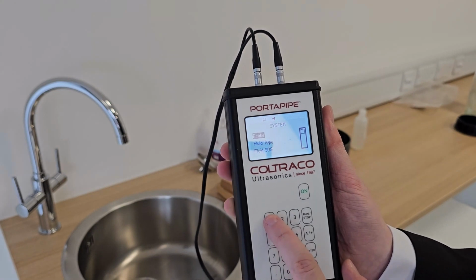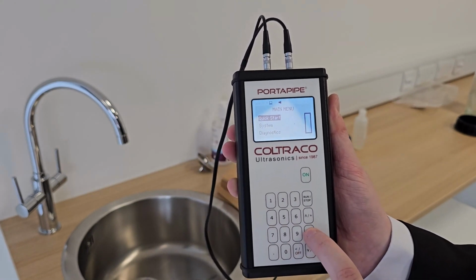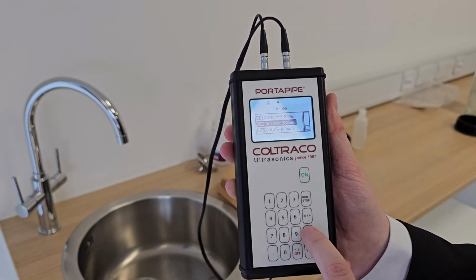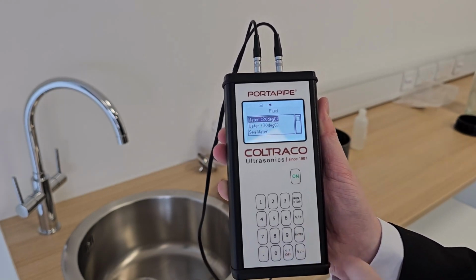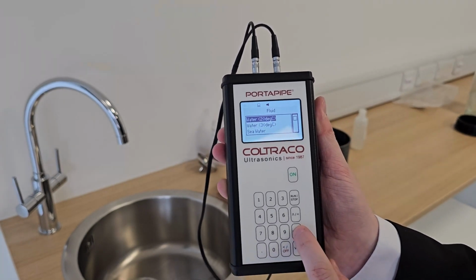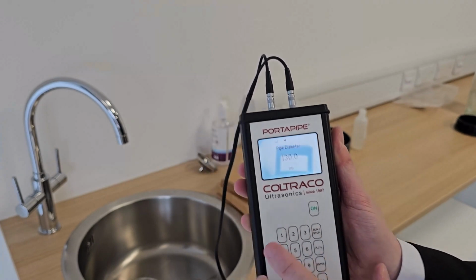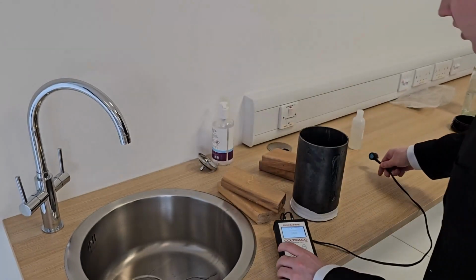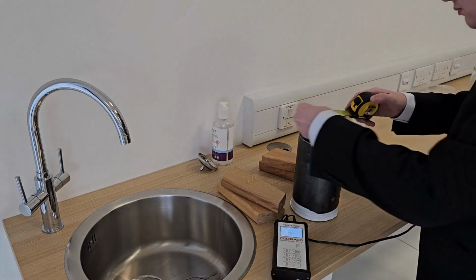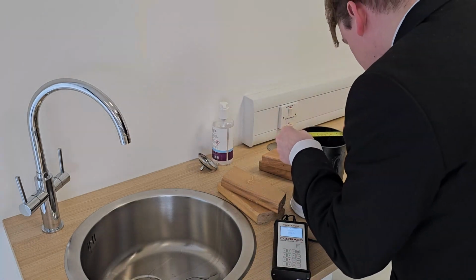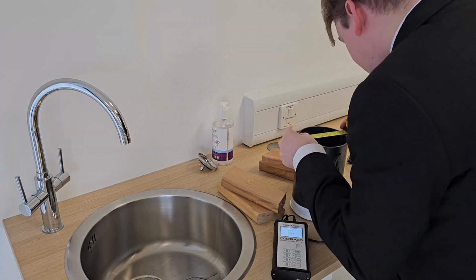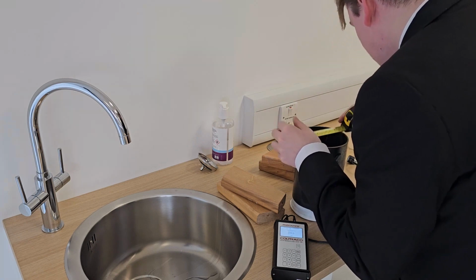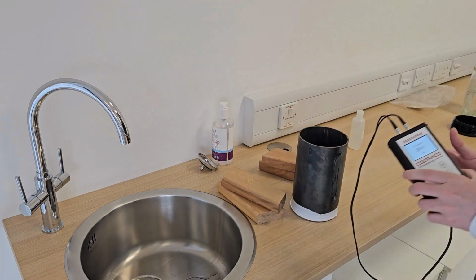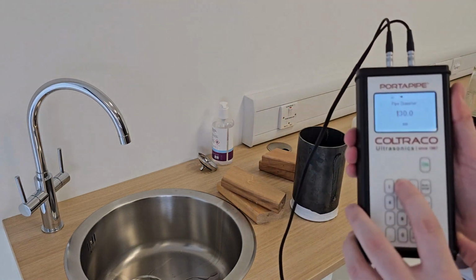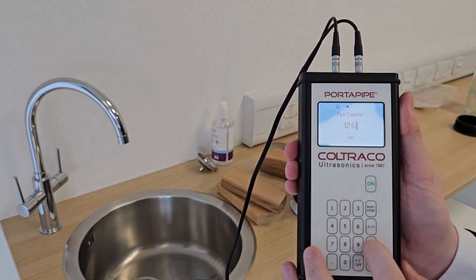Going back to the quick start menu to start again - still using the 2.5 MHz sensor, no change there, still testing with room temperature water. However, the pipe diameter has changed, so I'll quickly measure that. It is now 126mm - it hasn't changed by much, but it has changed a little.